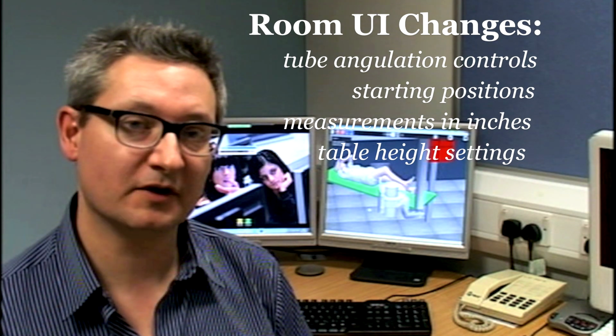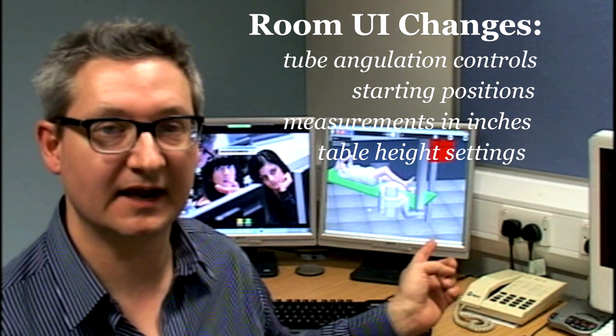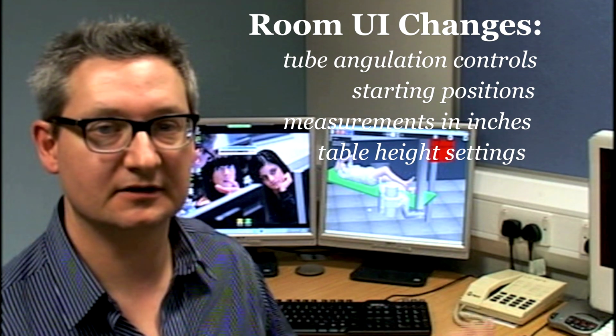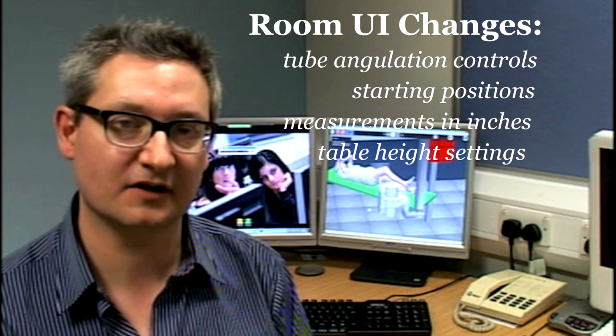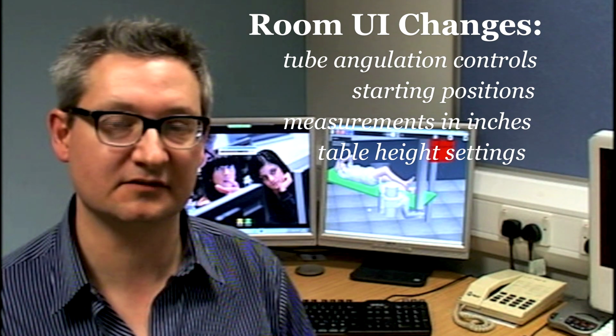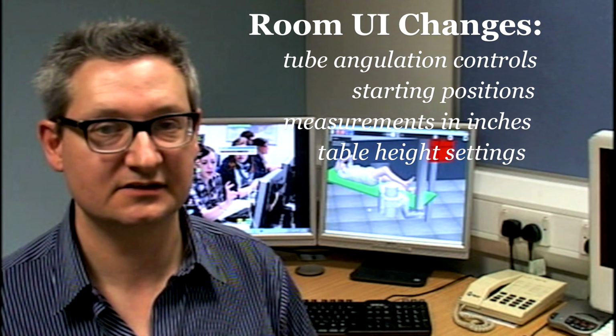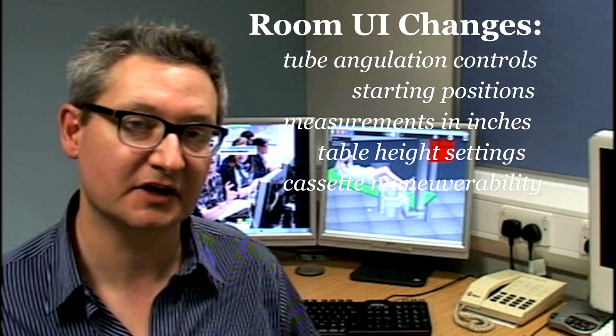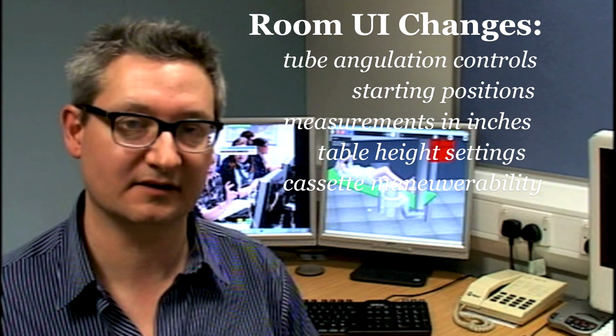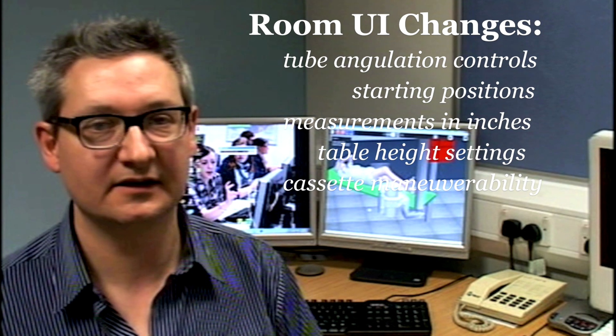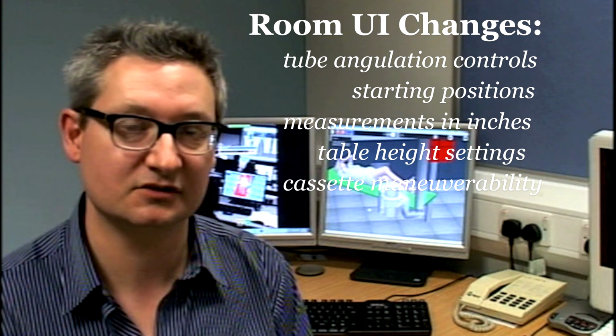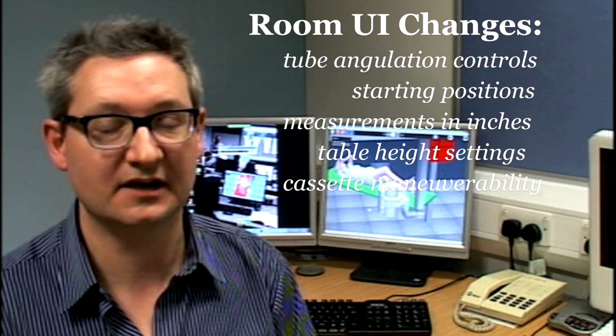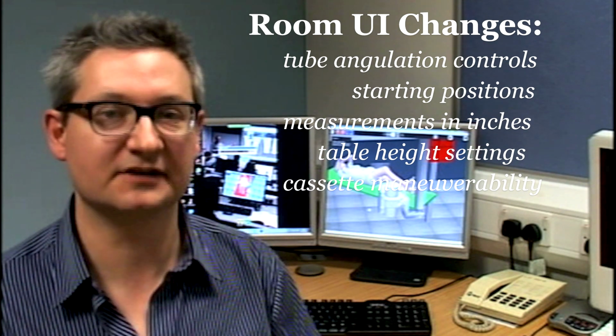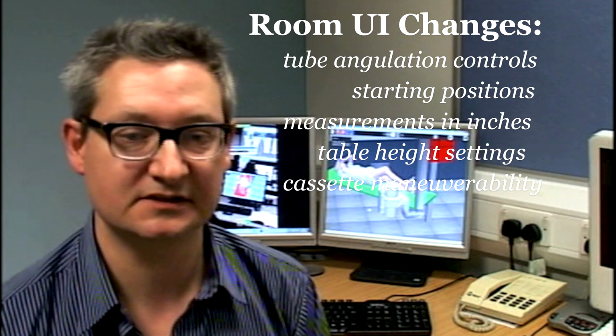In the trolley trauma module, which I've got up here now, or the gurney module, we've actually been asked to give more flexibility for where you can actually put the cassette. So now you can drag the cassette away from the bucky on both sides of the bucky and actually put it on the trolley and image between the legs. You can place the cassette to image a knee or an ankle. So that really adds a little bit more flexibility there.